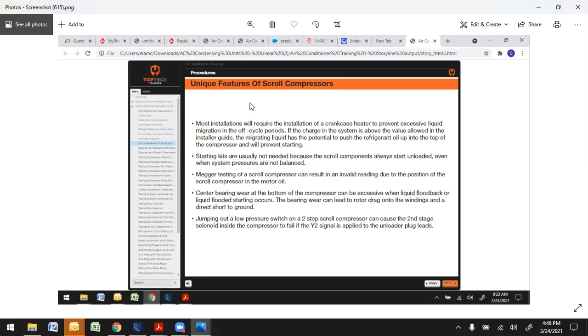Some unique features of scrolls. Couple highlights here. Starting kits are not always needed because the scroll components always start unloaded, even when the system pressures are not balanced. This is a big one, so if you're using a Megger or a Mega Ohm tester, if you meg a scroll compressor, it can result in an invalid reading due to the position of the scroll compressor in the motor oil.